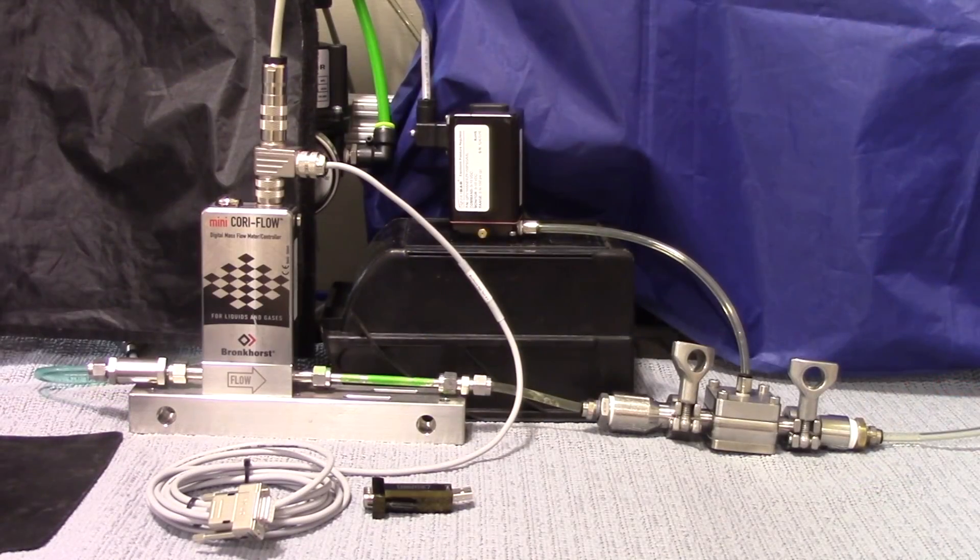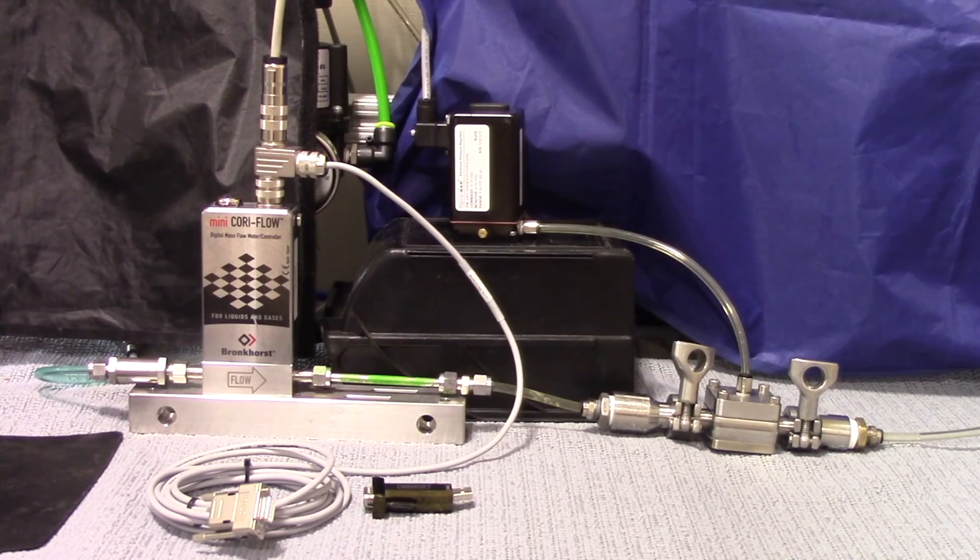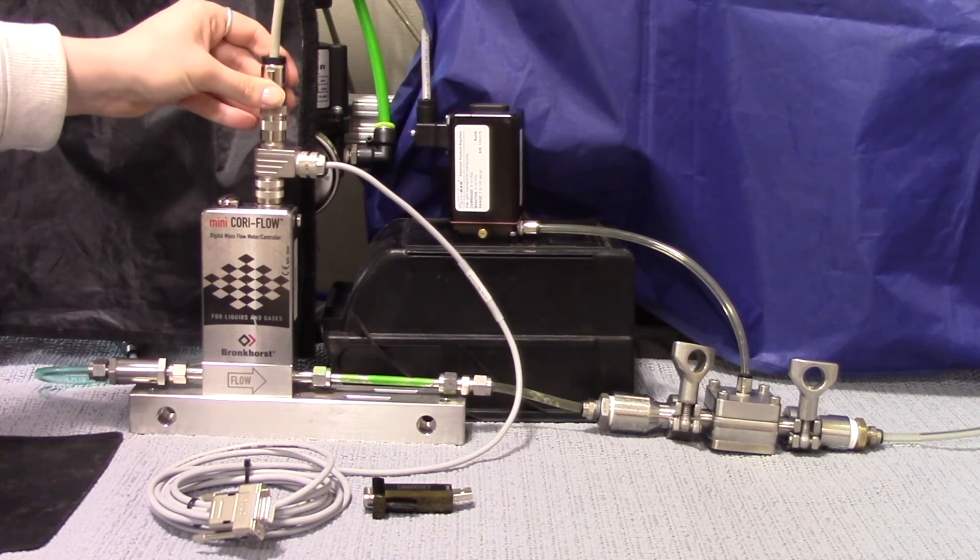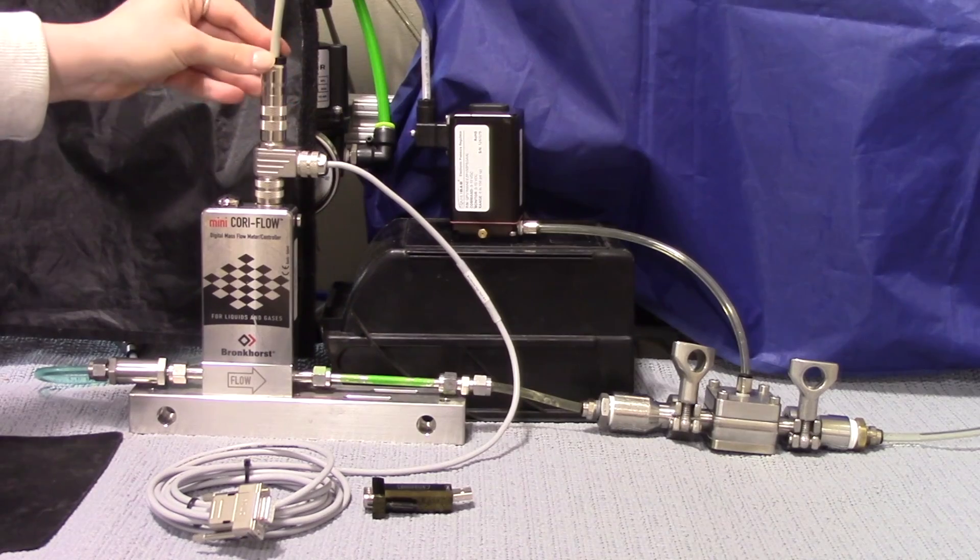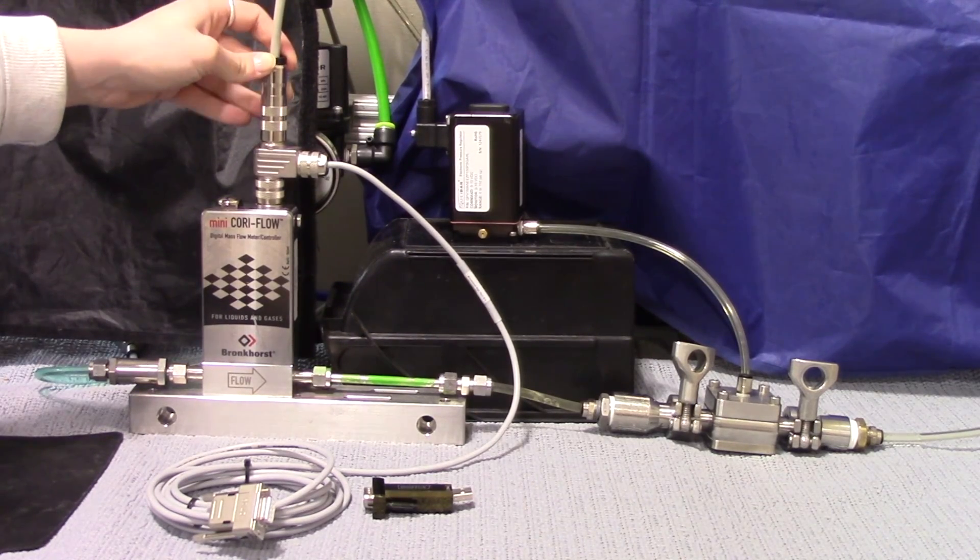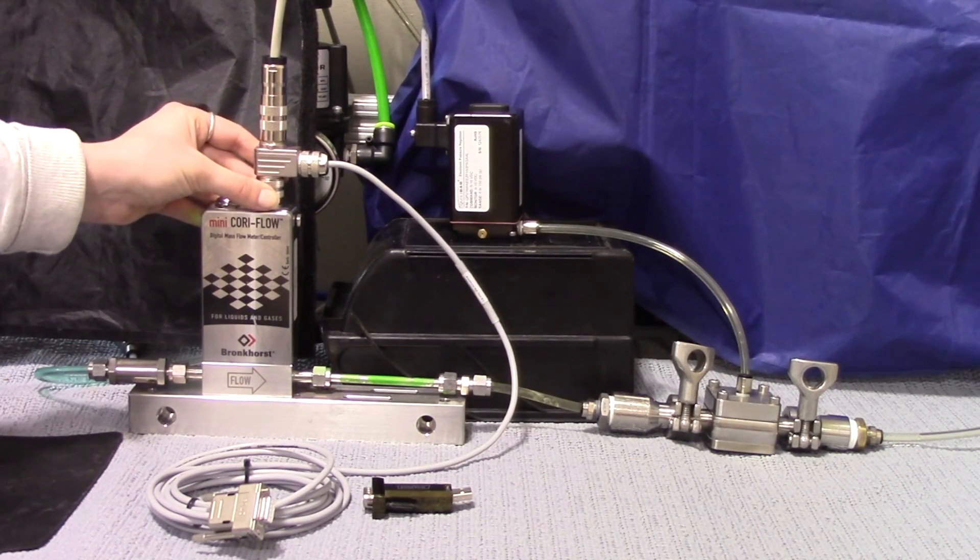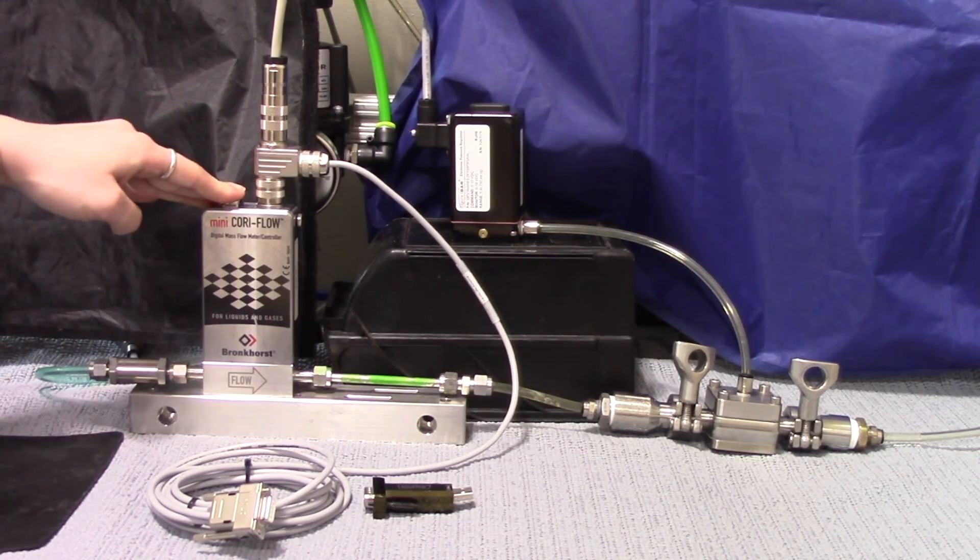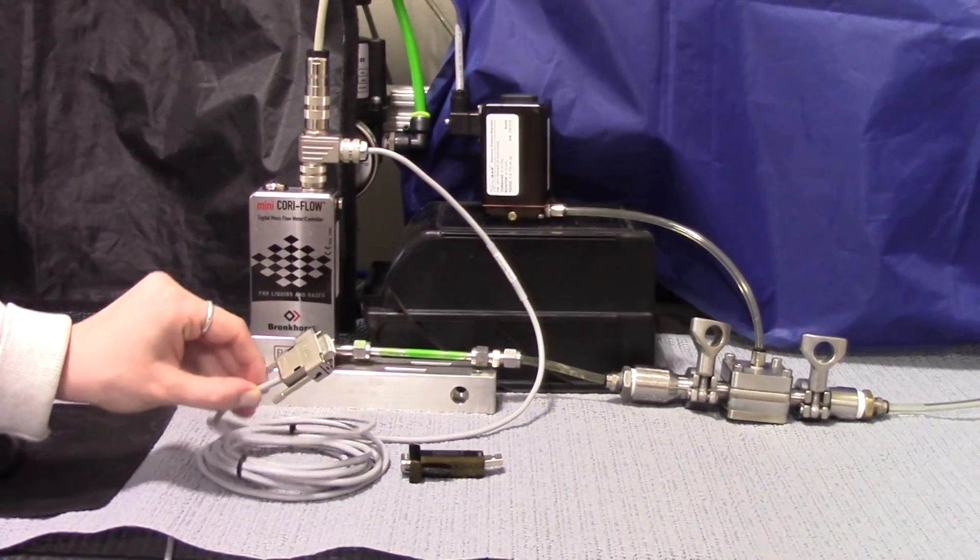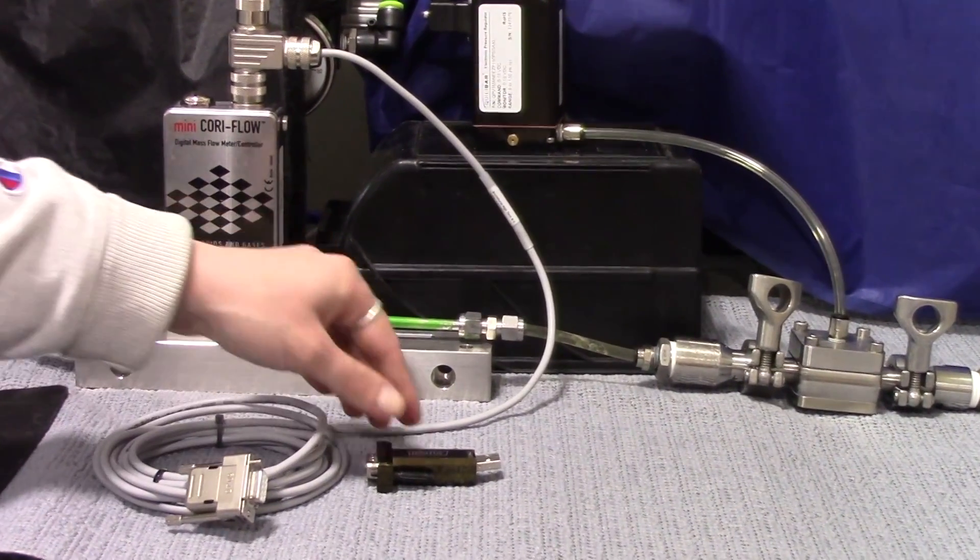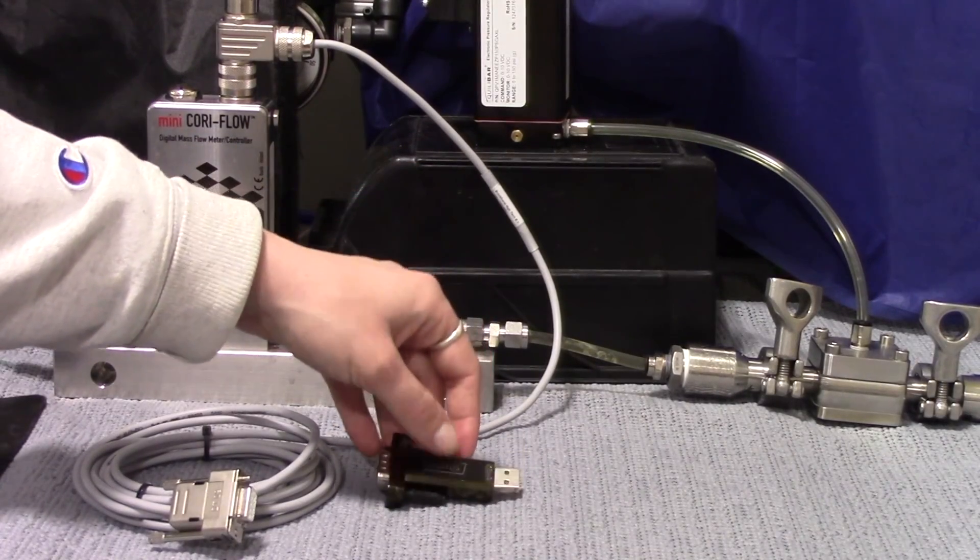It's pretty easy to get set up using a Bronkhorst flow meter in this application. Ours is powered externally using a 24 volt supply. You can find a pinout diagram for that on Bronkhorst's website in the flow meter's manual. There's also this cable that tees in that allows us to communicate between a laptop and the flow meter using RS-232 communication. In order to interface with a laptop, we need this RS-232 to USB connector.